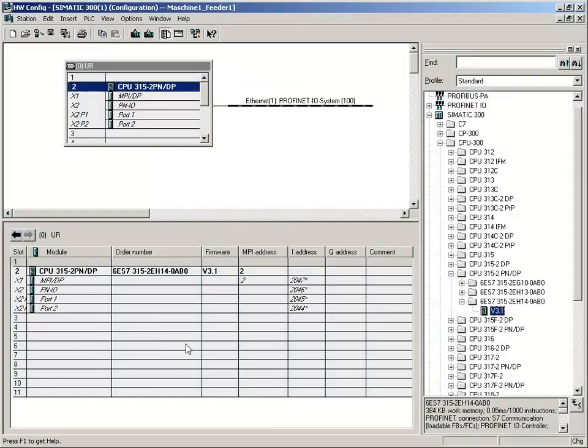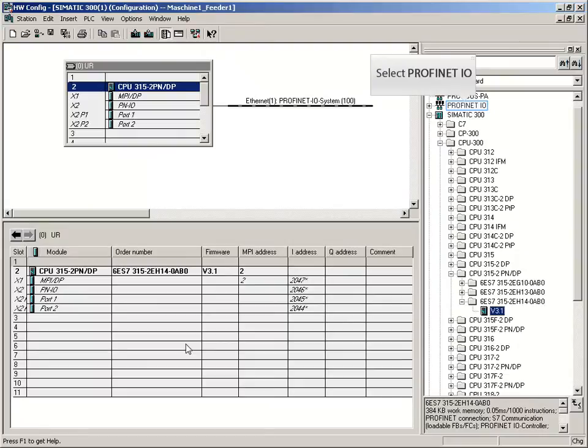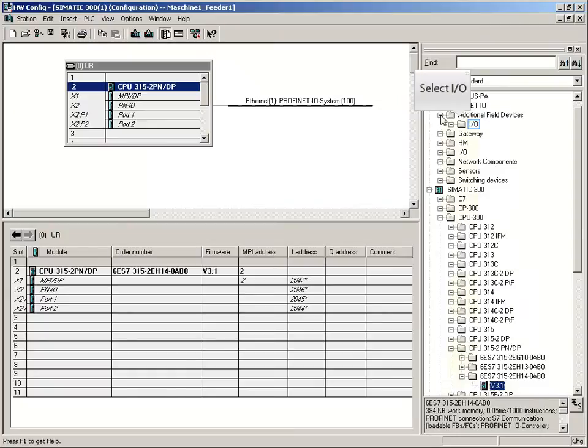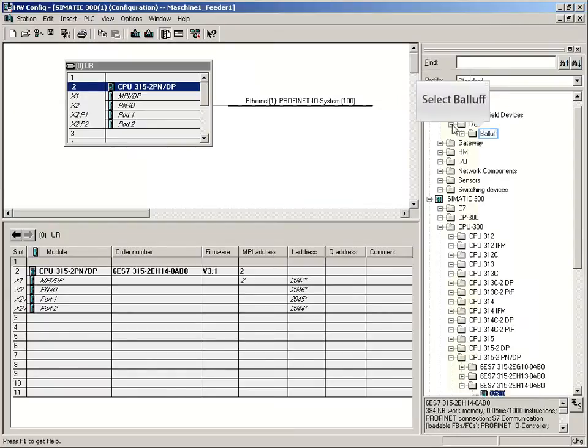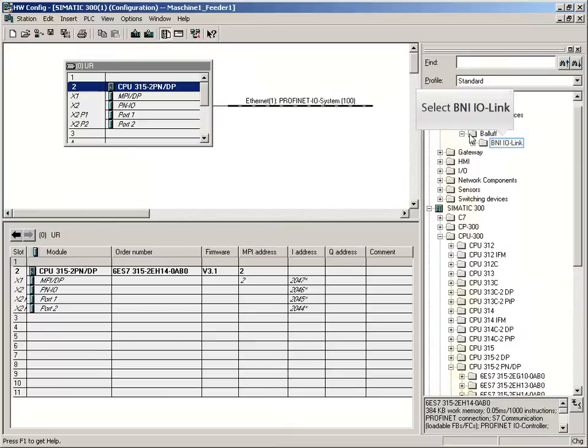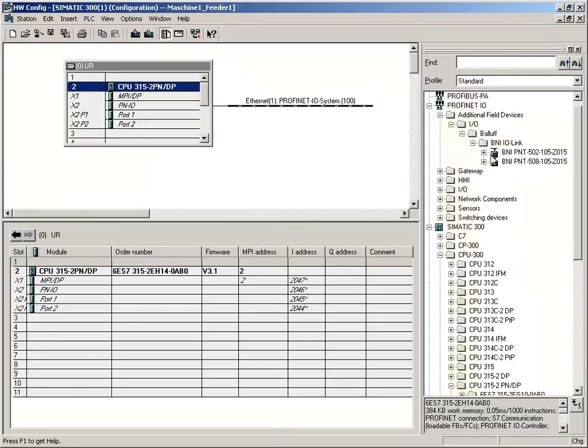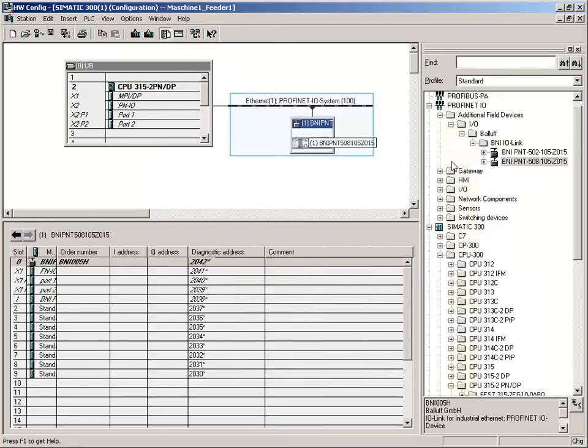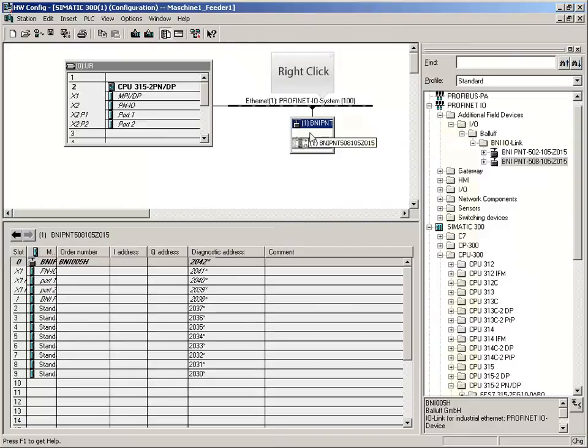Next step is to provide the Profinet IO system with field devices. Therefore we open Profinet IO, select additional field devices, and there the IO link master. The appropriate GSDML file has to be installed in advance. Bring the Profinet IO master via drag and drop to the Profinet IO system.